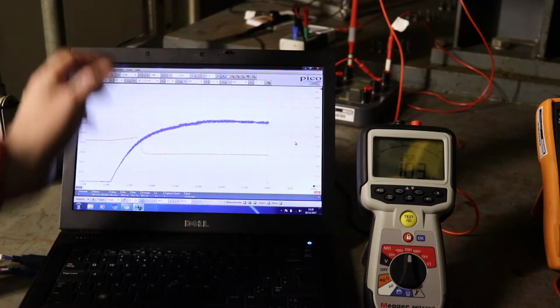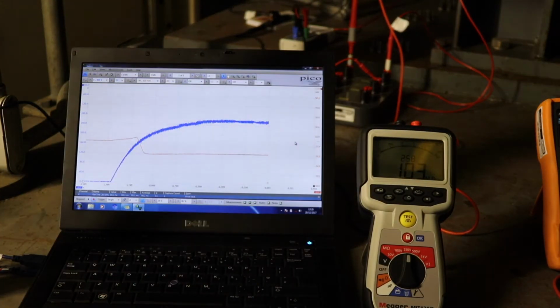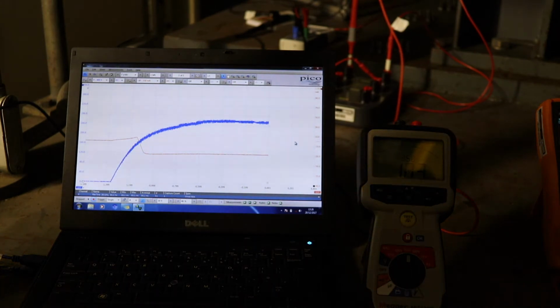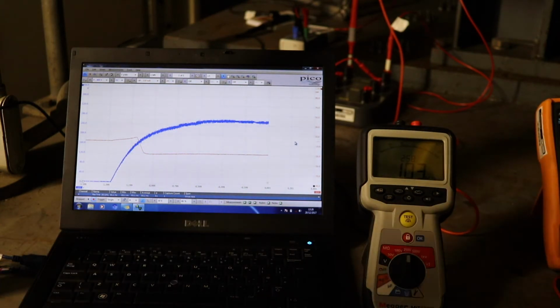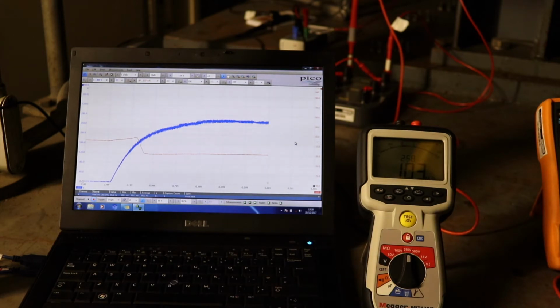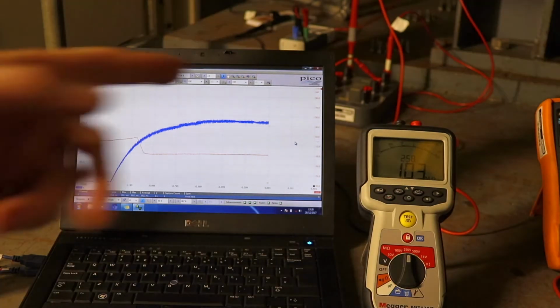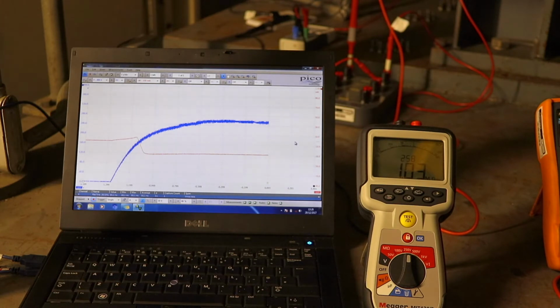Unfortunately, doing that is actually creating an issue on the reading. It's only getting above 2 megohms, which I presume is the input impedance of the differential probe, and it's being affected because it's linked to the actual output of the insulation tester. When I'm doing it without the current probe connected up, then the voltage reading will form normally and you will still get the actual reading of the rotor winding insulation.